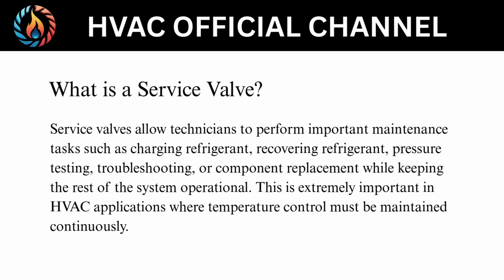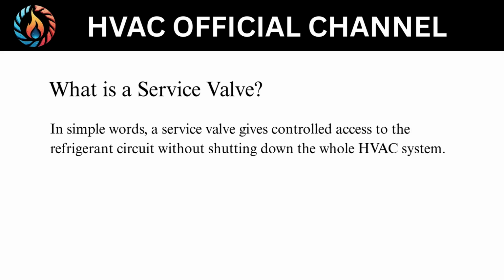Service valves allow technicians to perform important maintenance tasks such as charging refrigerant, recovering refrigerant, pressure testing, troubleshooting, or component replacement while keeping the rest of the system operational. This is extremely important in HVAC applications where temperature control must be maintained continuously. In simple words, a service valve gives controlled access to the refrigerant circuit without shutting down the whole HVAC system.